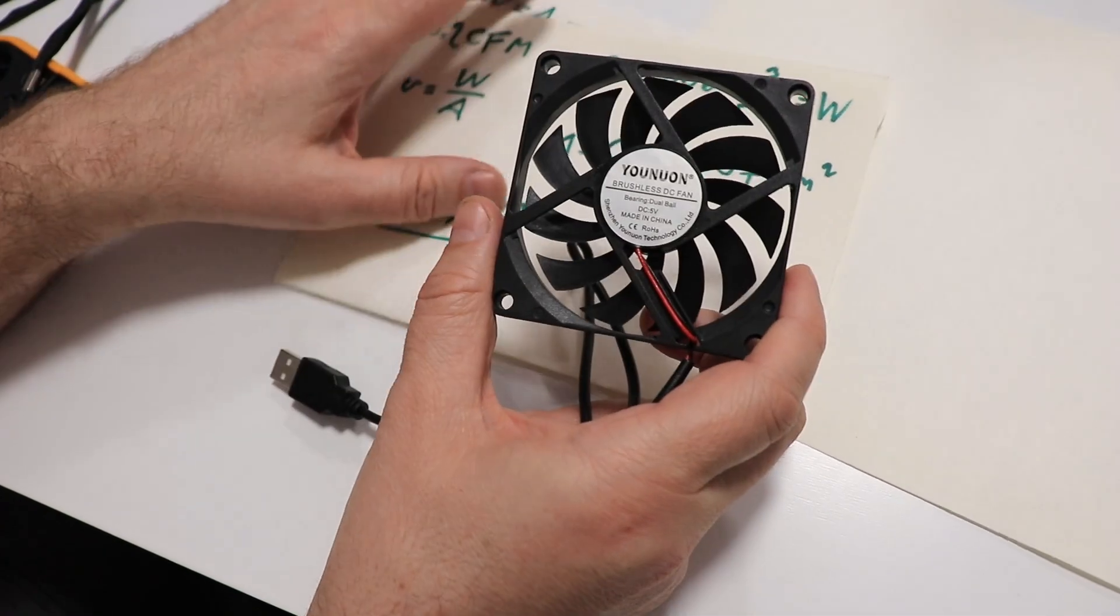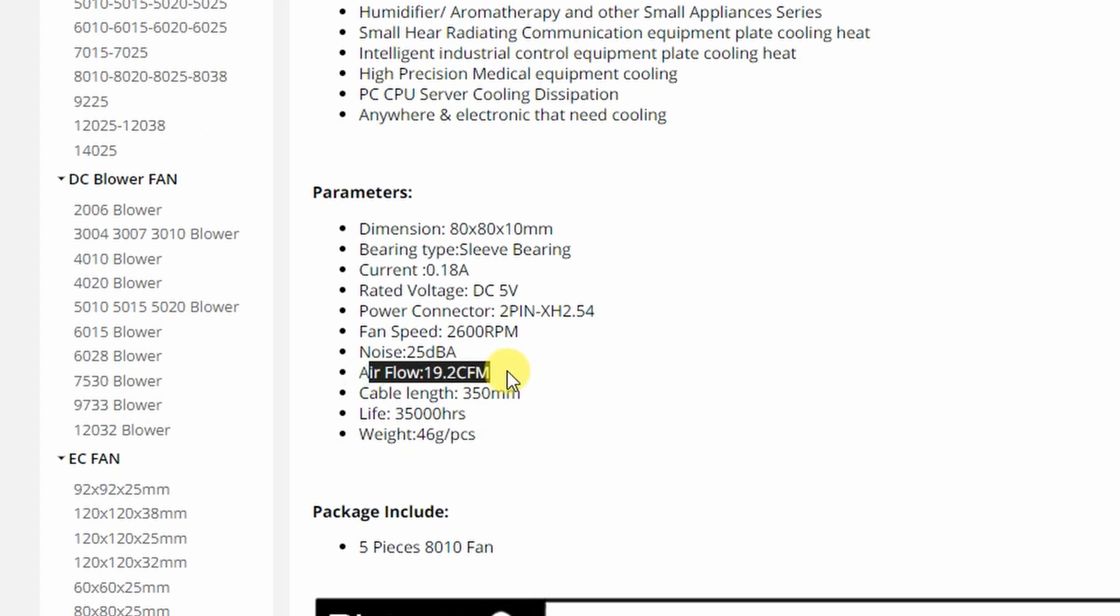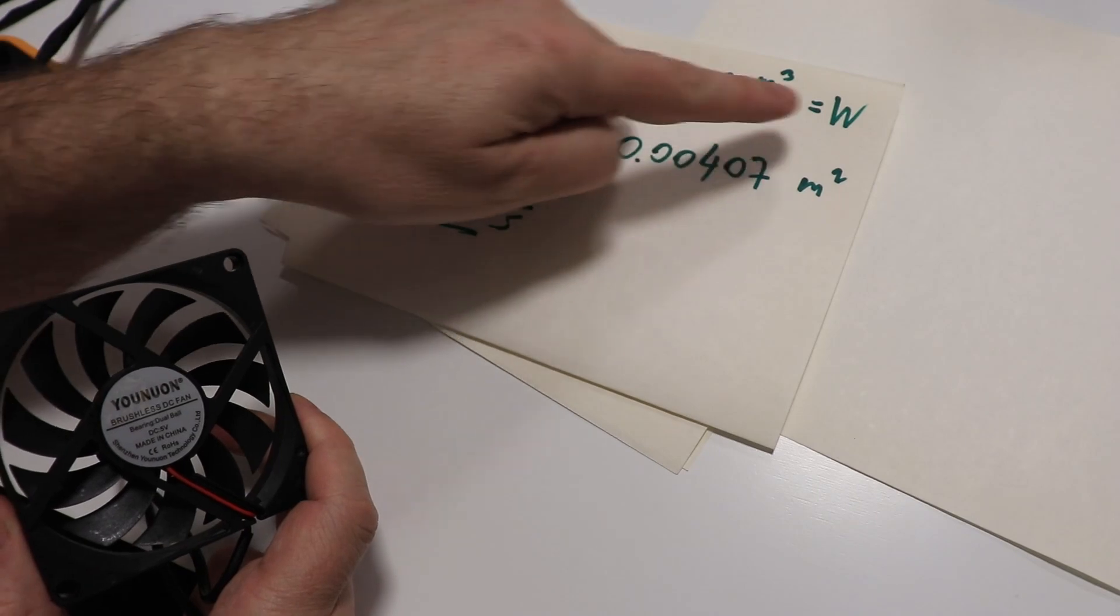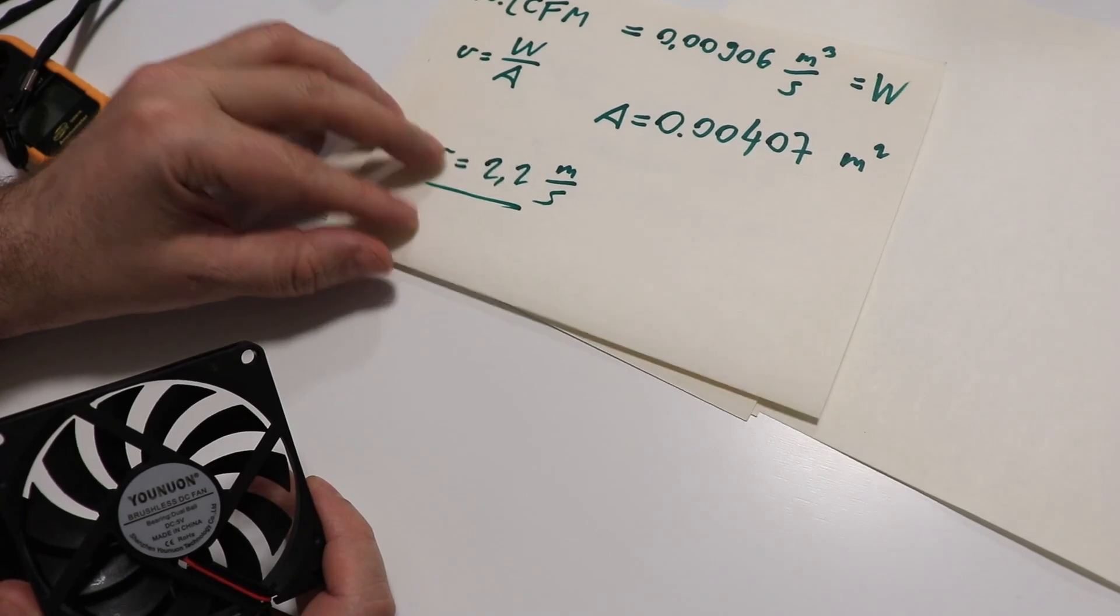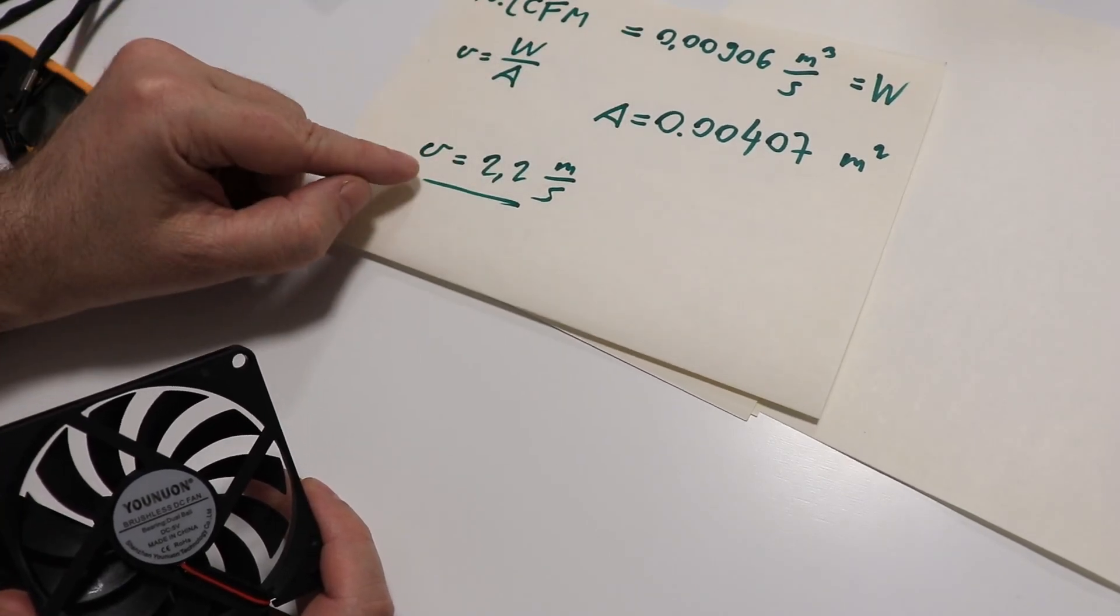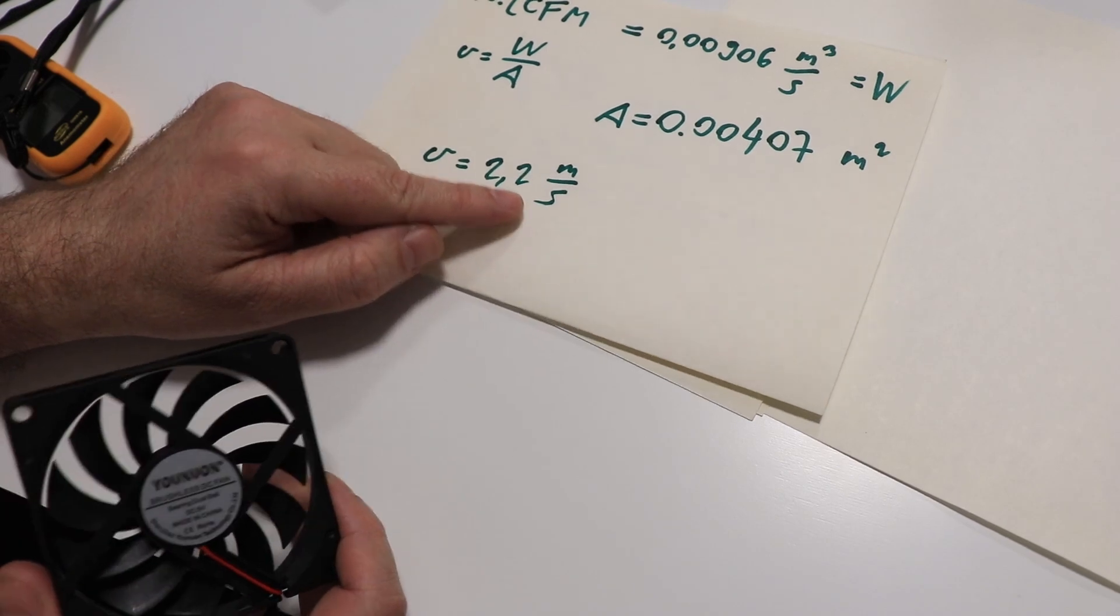I found some data about this fan. On internet I found that the flow rate is 19.2 CFM cubic foot per minutes. And I can convert it and it is 0.009 approximately cubic meter per seconds. So this is the cubic flow rate, and I have to divide this with the area. The area I already calculated in the previous calculation. And this means if I divide these two numbers I should get approximately 2.2 meters per second velocity. Let's measure them.